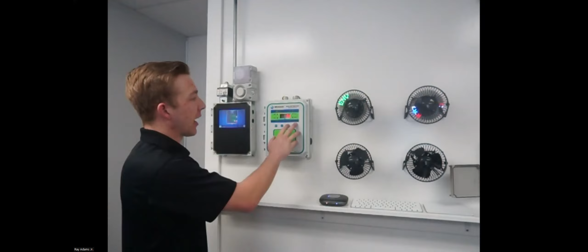We do see a lot of applications where there is a much more sophisticated sequence of operations. You may have several different zones or floors of a parking garage that you're working with, as well as multiple different set points. We deal with Amazon and their distribution centers, and they particularly like set points of 12, 25, 75, and 100. So those are 4 different set points that they spread across multiple different zones, controlling multiple different sets of ventilation equipment.